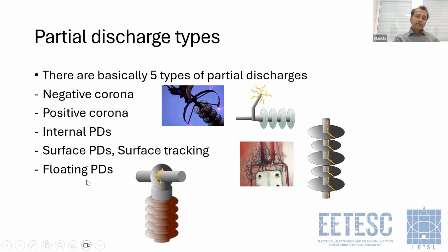And finally, we are having these floating partial discharges. Floating means the partial discharge happens between two different voltage levels, for example, floating voltage. As an example, in this case, there is this support insulator clamp, and through this a high voltage conductor is going through. So in this case, these two conductive elements might have two different voltages, so there might be tiny discharges that can happen between these two conductive parts. But these kinds of things are not that harmful, and it is a kind of non-effect.